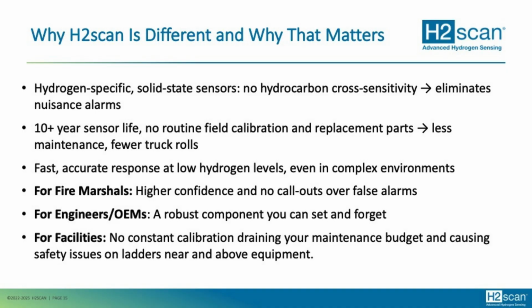So that's where H2scan comes into play. We have hydrogen-specific solid-state sensors. There's no cross-sensitivity to other hydrocarbons or any solvents or anything of that nature that would create any kind of nuisance alarms. So we've eliminated all of that. Our sensors have over a 10-year life. There's no calibration, there's no replacement parts, and there's nothing you have to do to it over its service life.